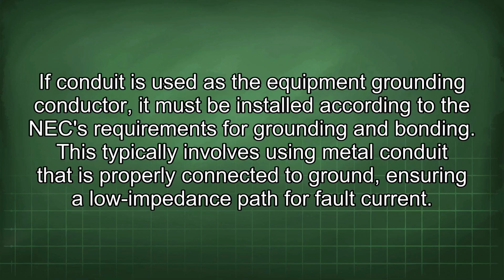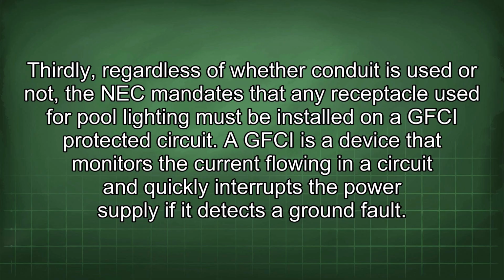Thirdly, regardless of whether conduit is used or not, the NEC mandates that any receptacle used for pool lighting must be installed on a GFCI protected circuit. A GFCI is a device that monitors the current flowing in a circuit and quickly interrupts the power supply if it detects a ground fault.